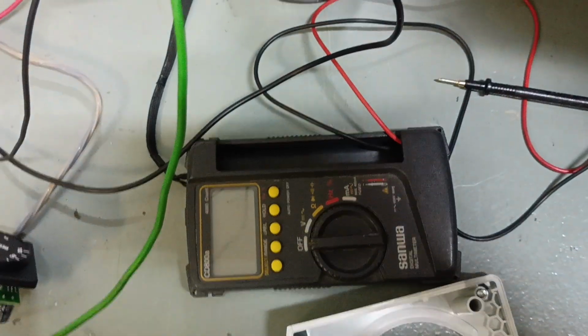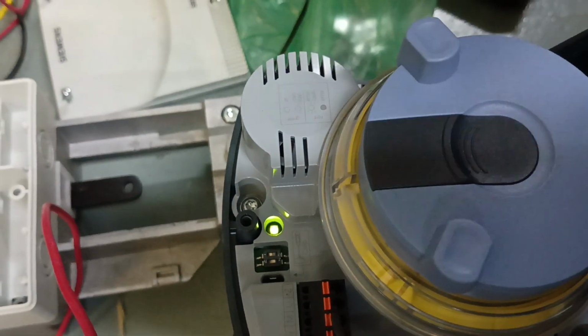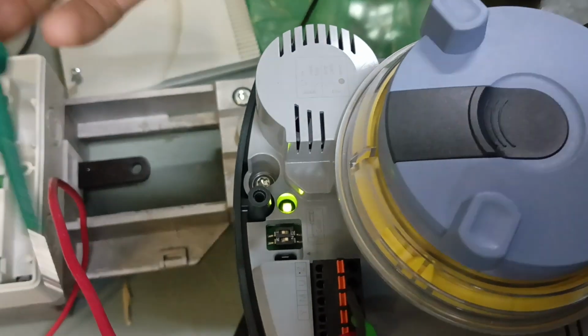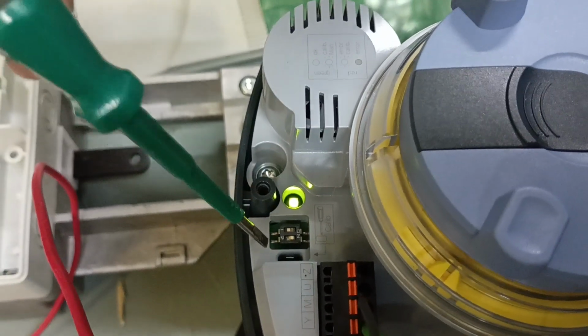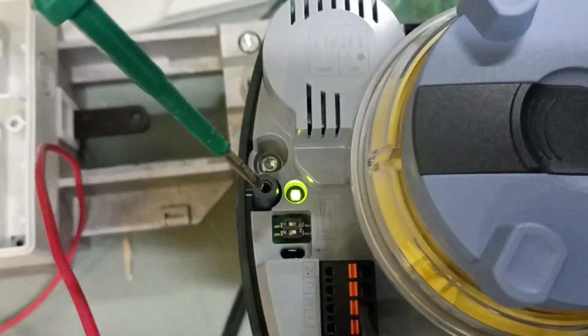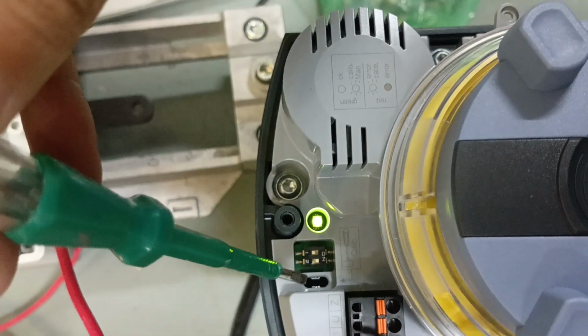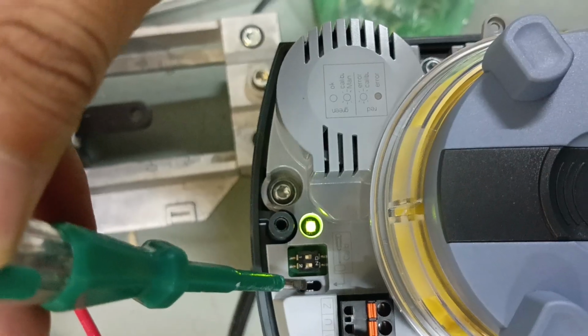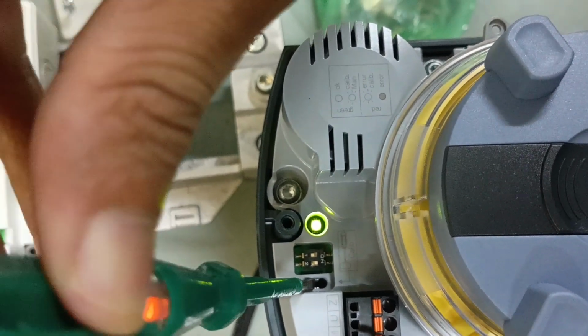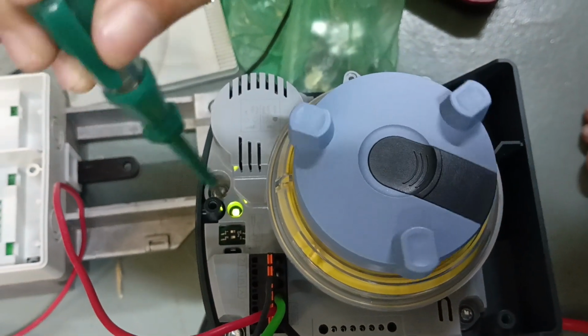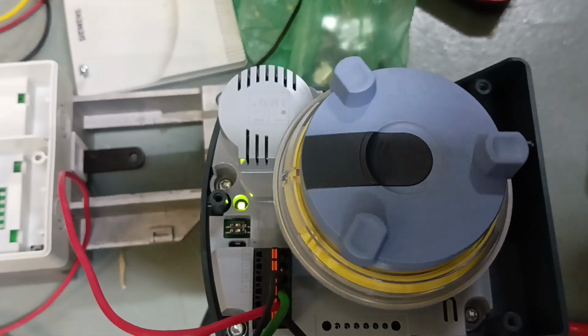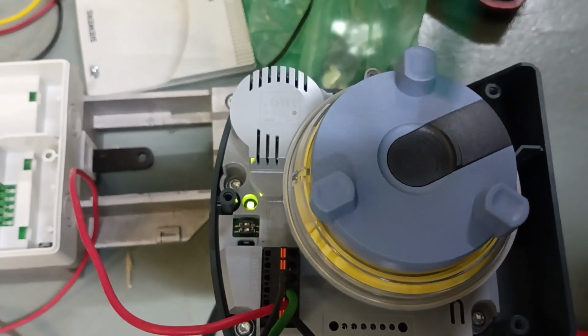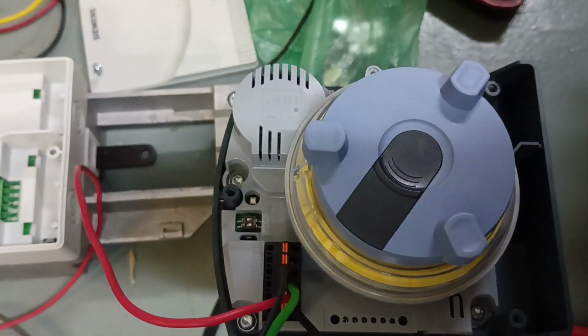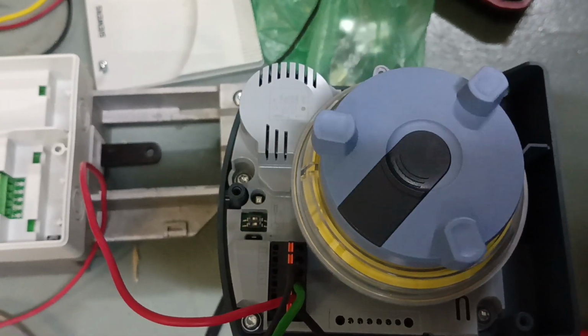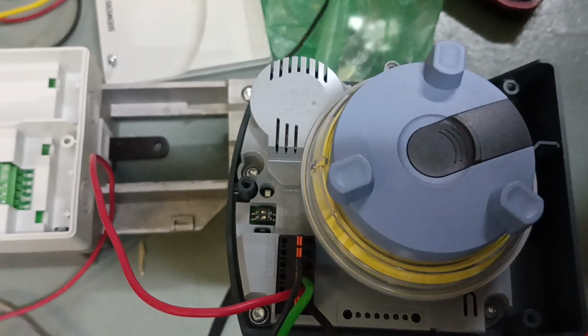If you want to do auto calibration, this model can do it. You take a test pen and insert it into this hole, and hold a bit. This one blinking means it's doing auto calibration, so the actuator will go close and then open. This is to detect how far the valve travels between the close and open positions.